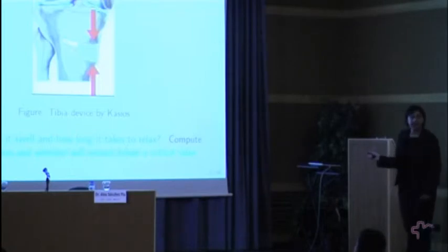Now, every material component swells, absorbs water, at a different ratio. So what happens is that at interfaces, and in this case you could think of the interface between the implant and the bone itself, there is a high concentration of force. This high concentration of force may cause what's called a blistering instability at the contact, and eventually make the device fail because it falls apart. So now our question is, how much does it swell and how long does it take to relax? One issue that Dr. Regura also talked about is the concept of residual stress.